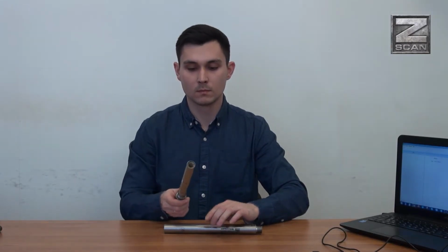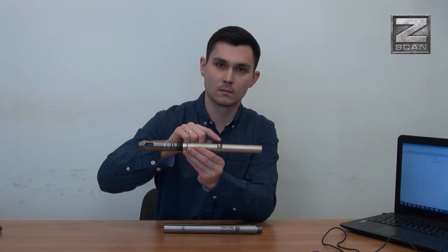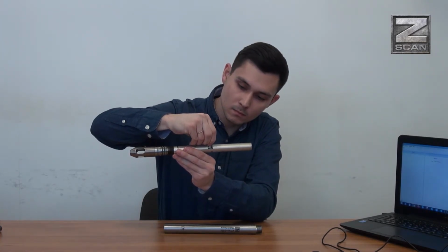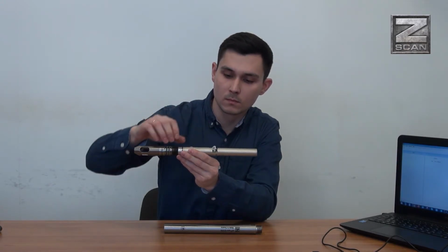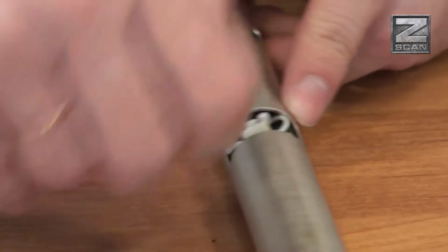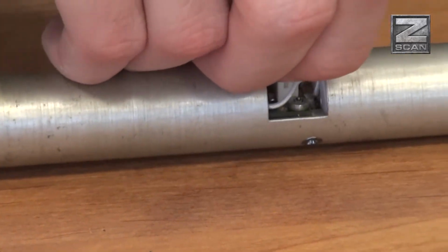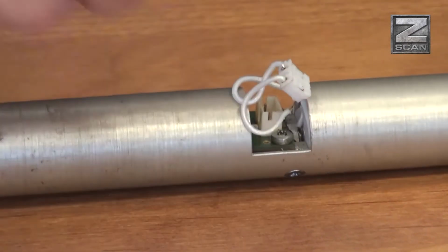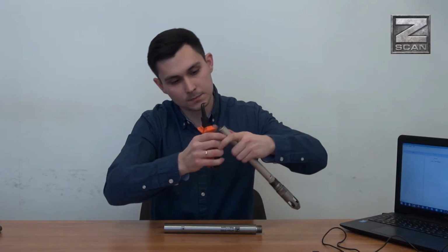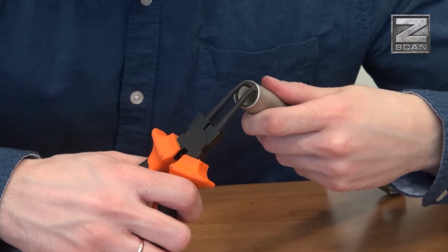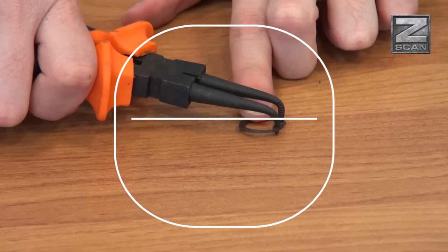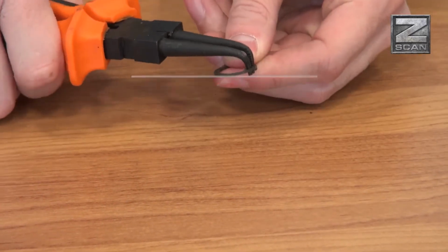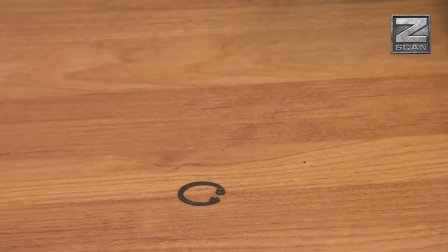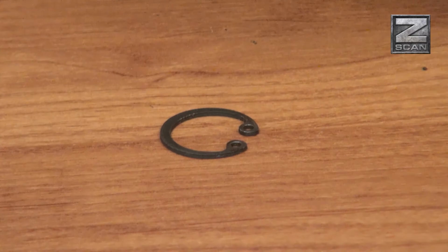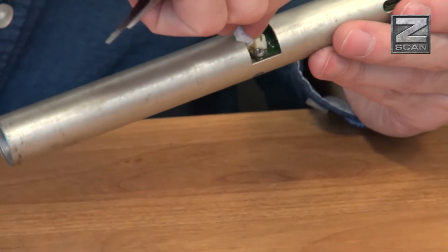There is a battery compartment at the rear end of the sensor assembly. At the beginning of the battery compartment is the battery connector. Disconnect the old battery from battery connector. Remove the retaining ring with pliers. Important: be very careful when doing this, otherwise you may lose the retaining ring. Remove the battery and the inserts.